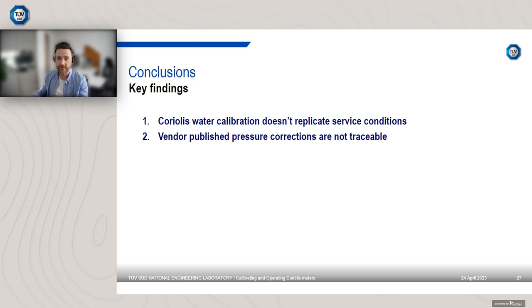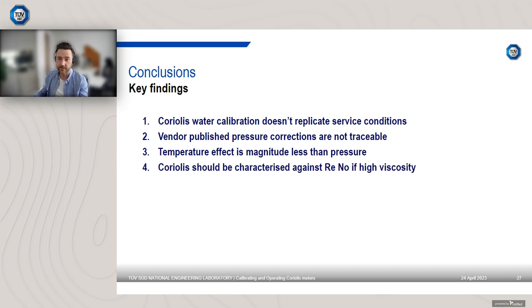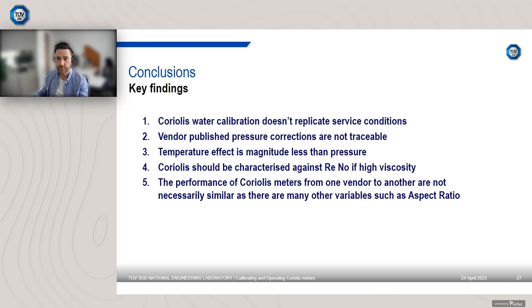If you're only trying to achieve, say, 5% measurement uncertainty, it's a low-value product, there's no strict regulations or agreements, then potentially a Coriolis water calibration does replicate your service conditions because of your high uncertainty. However, for most applications, when you're trying to achieve a low measurement uncertainty, a water calibration doesn't replicate service conditions. Secondly, the vendor published pressure corrections are not traceable, so we always recommend that you ascertain your device's pressure compensation factor at a traceable laboratory.